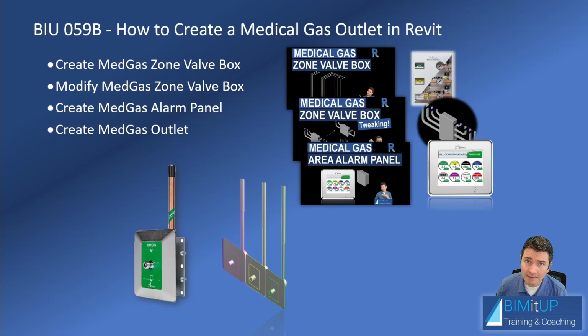So these are outlets that can be used for any type of medical gas: oxygen, nitrogen, medical air, medical vacuum, waste anesthetic gas disposal. And these that you see here are intended for wall mounting, so head walls or any other type of walls. But they're very flexible because they're not hosted, so they're free to be placed wherever you want them. You can place them even on a boom if you want to. Okay? See you in Revit.